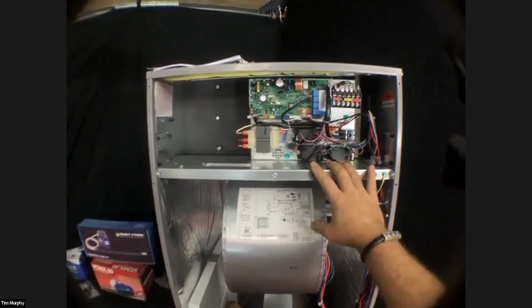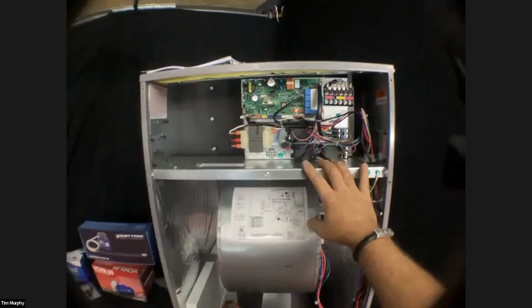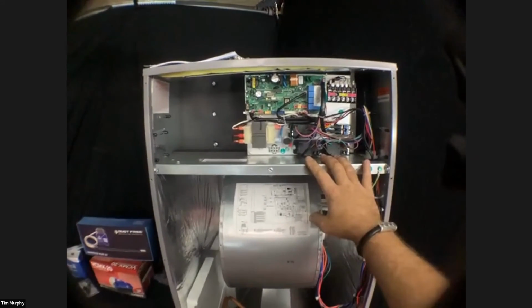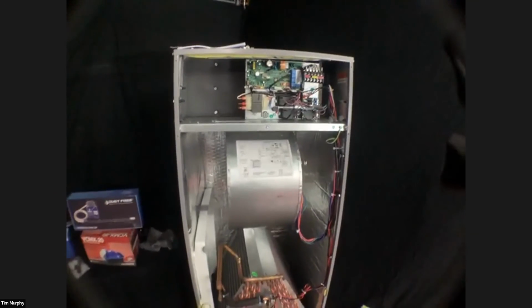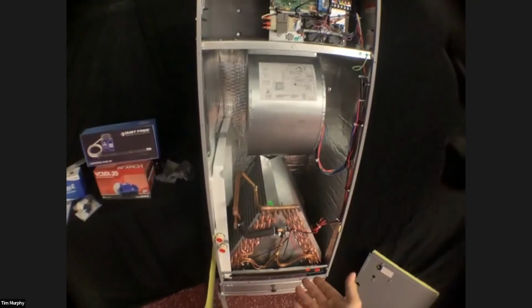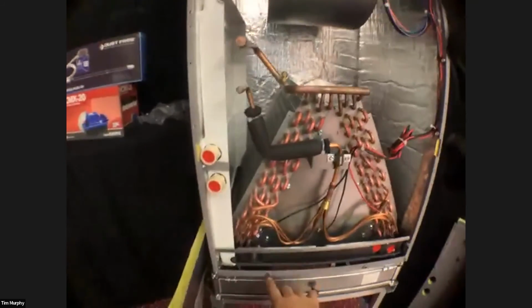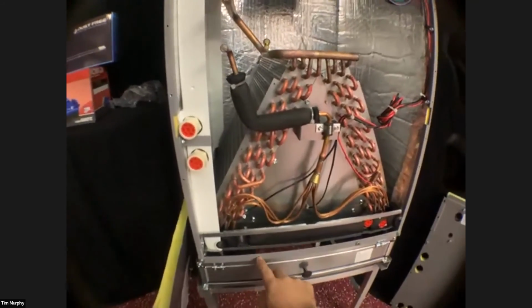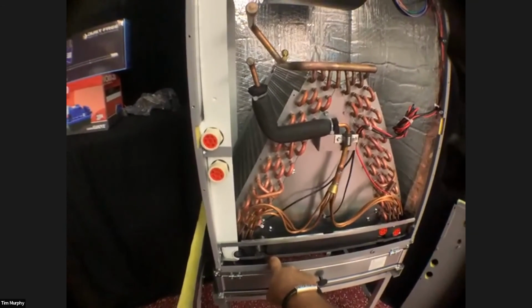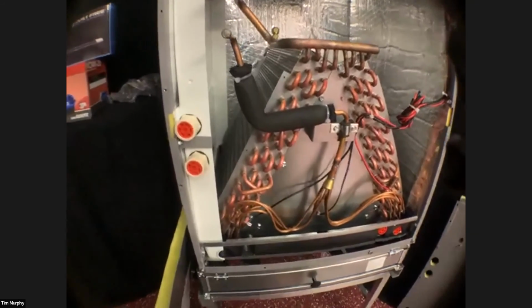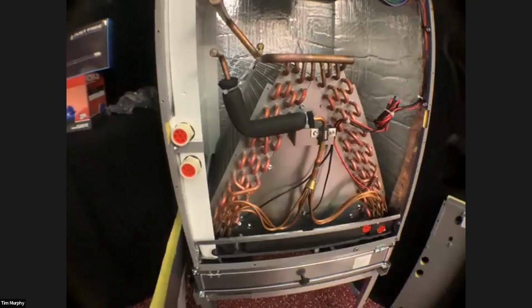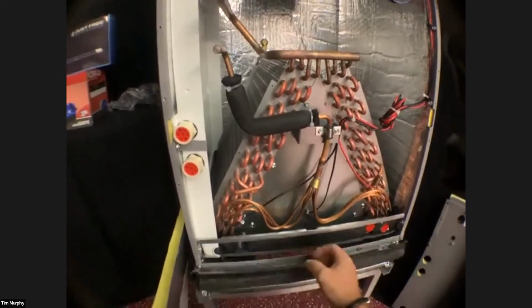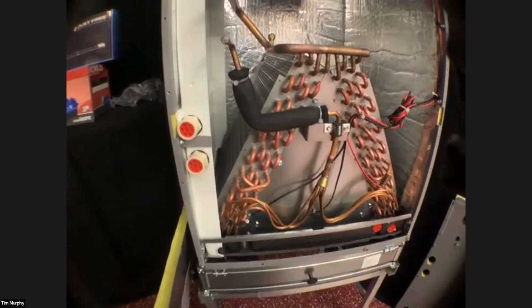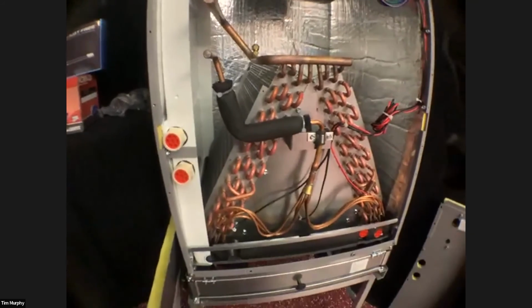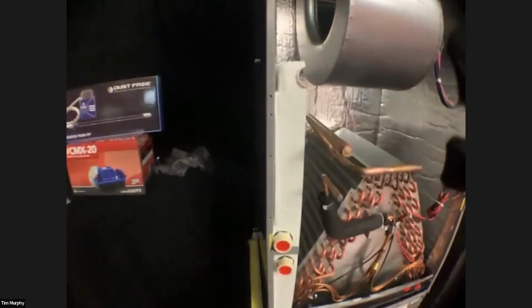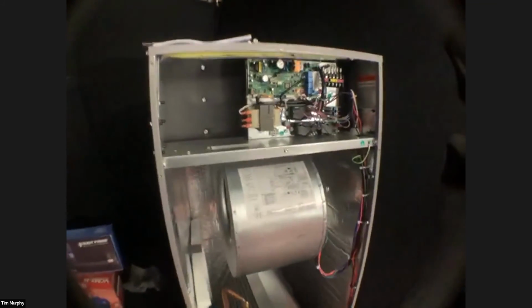We want to see 0.5 static in any inverter system, on any system really. You really don't want to go above 0.5, because once you do, that's when you start running into issues. If you're measuring static pressure on these, you want to measure in between the coil and the filter. You don't want to include the filter. You can take one of these screws out, put your probe in there, get it between the filter and the coil, and that'll allow you to get a proper reading. If you're measuring on this side of the filter, then it's definitely not where you want to be. I went out to a job not too long ago, and the guy gave me static pressure readings measured before the filter, and it made a half inch of static difference, which is huge, a little less than doubling.